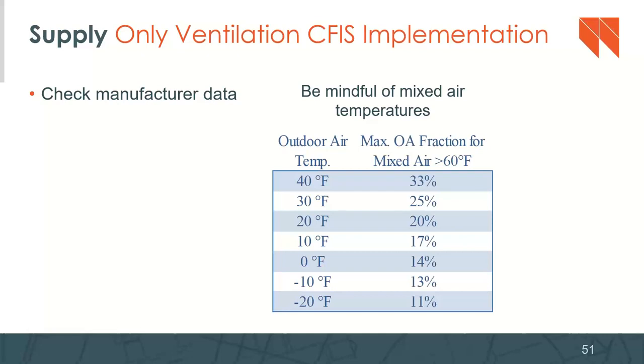Other things to keep in mind with this sort of setup is to check the manufacturer data of the air handler to know how much outdoor air you can bring in at a given outdoor temperature. So this is reading that at 10 degrees Fahrenheit outside, you only want to bring in 17% of the air that the air handler is moving. So you want to be aware of that kind of information before you go ahead and implement this kind of system, so that you can bring in the right amount and select the right air handler to make this work.